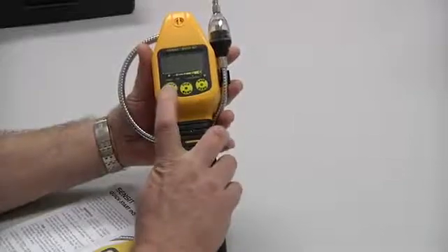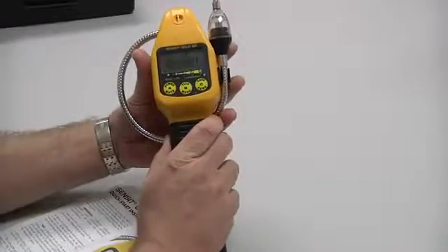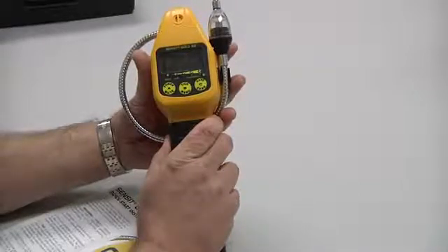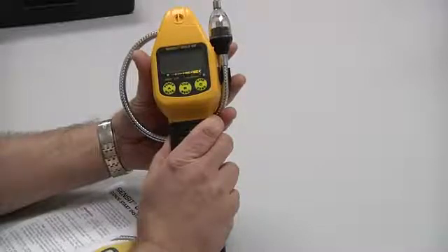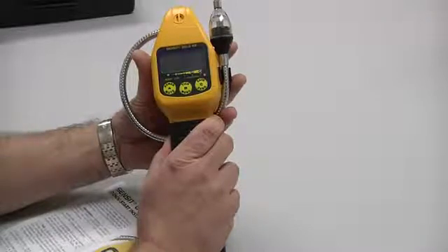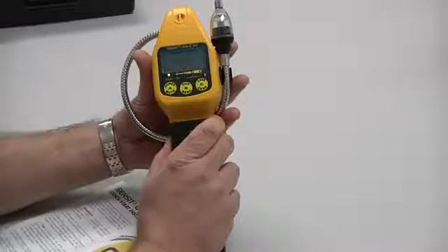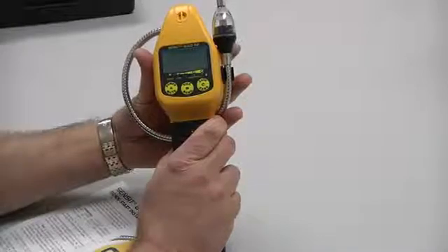To turn the instrument on simply push the A button, hold it down until the display begins to illuminate. The instrument will go through a warm-up period in which time it is doing a complete system check. During the system check the microprocessors will go through to identify any sensor issues, any pump issues, or any other problems that may exist within the instrument.